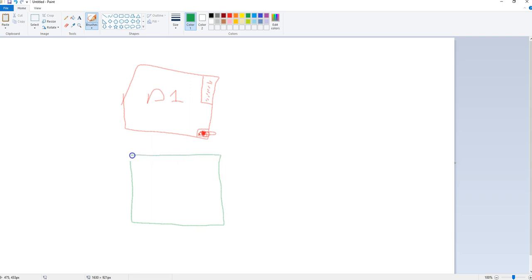Now, here's the cool thing. The same thing happens for DICOM server 2. Its configuration files are stored right over here. There's its configuration file, and it has a log file of all the patients that went through it. Now guess what? That gets backed up on DICOM server 1.